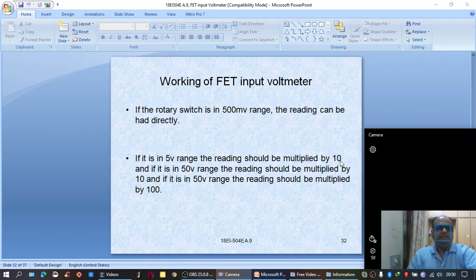When the range switch is changed to the second position, the reading actually would be 0.5. It has to be multiplied by 10 in the second range. And in the third range, the 50 volts range, it has to be multiplied by another 10. For 0.5 to 5, multiplication by 10. Similarly, 5 to 50, multiplication by 10.